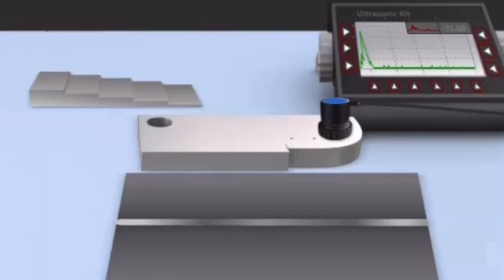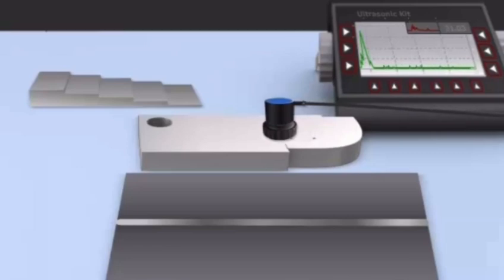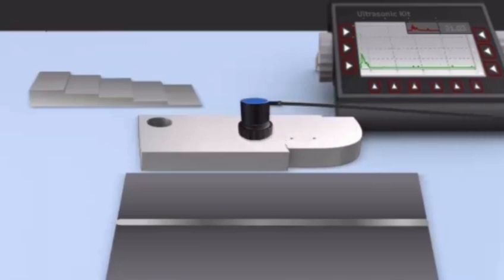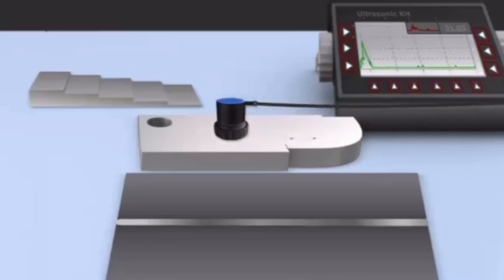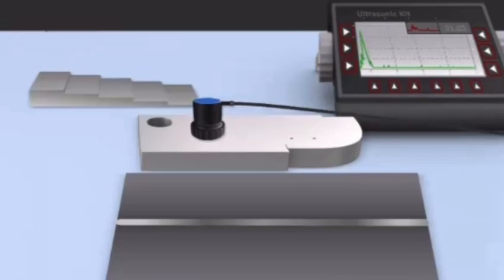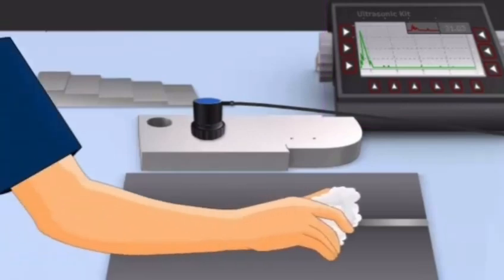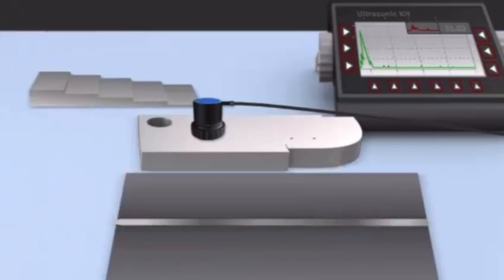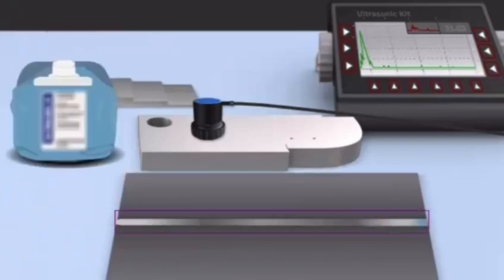First, the test equipment should be calibrated using the standard gauge block as shown. Check the settings with thickness and predefined defects. Here, the instrument should show the reading related to the gauge block. The test surface should be cleaned thoroughly. A thin layer of couplant should be applied over the test surface.